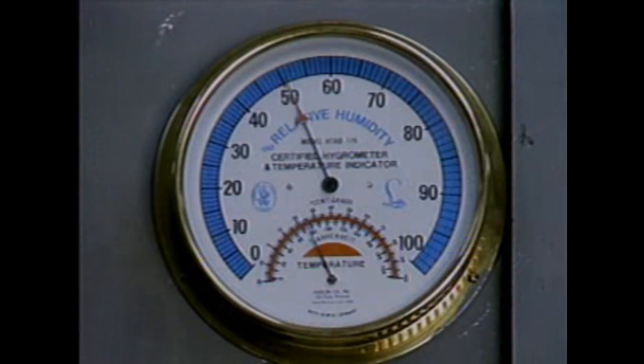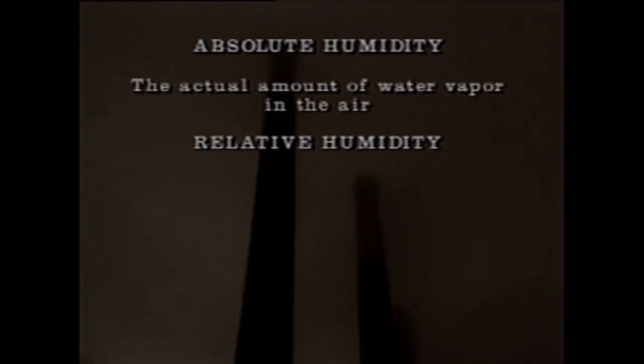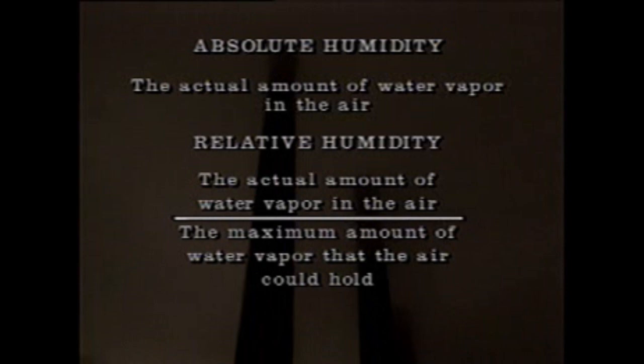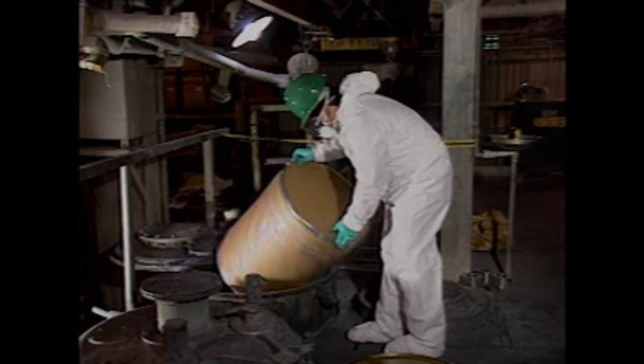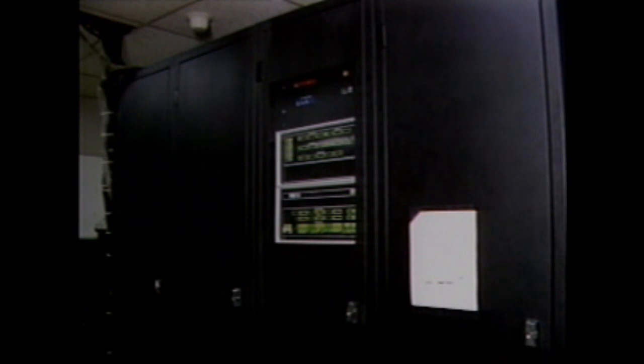Water is present in many process materials as well as in the air surrounding process equipment. Measurements of water content are often expressed as humidity or moisture. Humidity is a measure of the amount of water vapor in a given volume of air. Absolute humidity is the actual amount of water vapor in the air, often measured as ounces of water per cubic foot of air. Relative humidity is a ratio of the actual amount of water vapor in the air at a specific temperature to the maximum amount of water vapor that the air could hold at that temperature, expressed as a percentage. Measuring and controlling humidity is important because it can affect moisture-sensitive materials used in a process, as well as electronic equipment used to monitor and control the process.